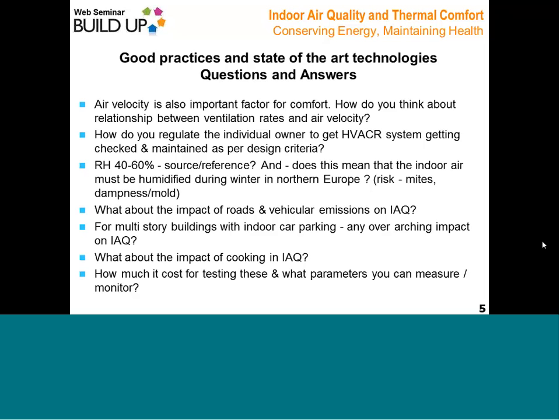In Sweden in the winter, even though you have very high relative humidity outdoors, it's still incredibly dry indoors — people get their moisturiser out because their hands are cracking up. I'm not sure I'd want to spend any energy on humidification in my building, but the 40–60% range is normally what you want to aim for. Unless it gets very cold, I wouldn't humidify for it.